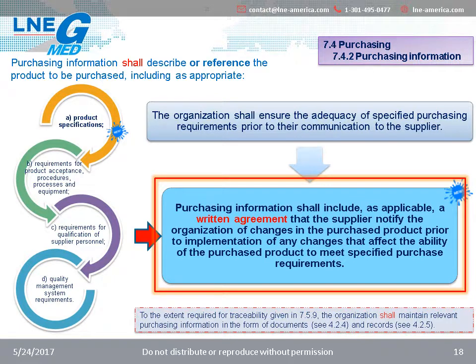If we now move to section 7.4.2, it is not specific to supplier control, but still includes some new requirements that are linked to the supplier initial control. This is where we can find the requirements related to a written agreement linked to change control. Purchasing information shall include, as applicable, a written agreement that the supplier notifies the organization of changes in the purchased product prior to implementation of any changes that affect the ability of the purchased product to meet specified purchase requirements. The format choice of this written agreement is left to the organization — some create contracts, some integrate it in purchase orders. There is no clear requirement in the standard about the format to be used.